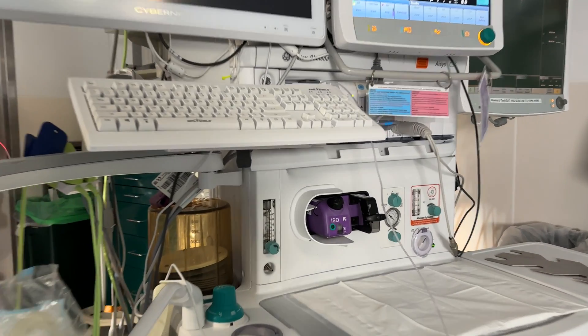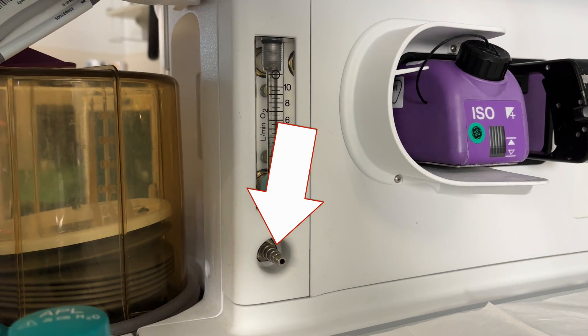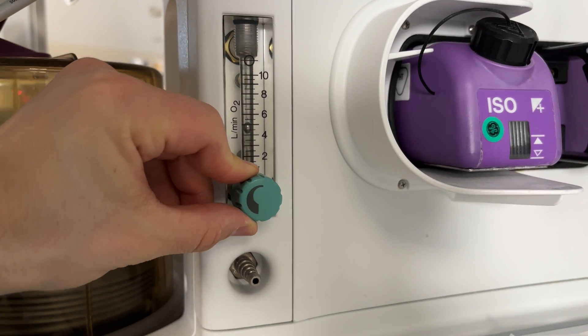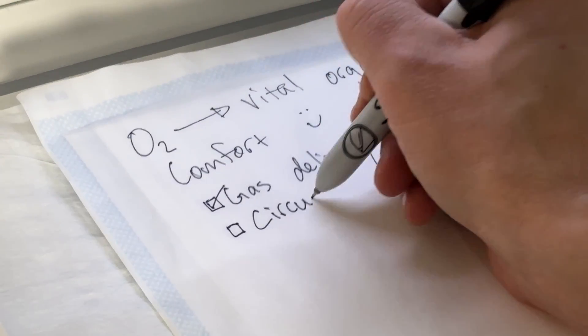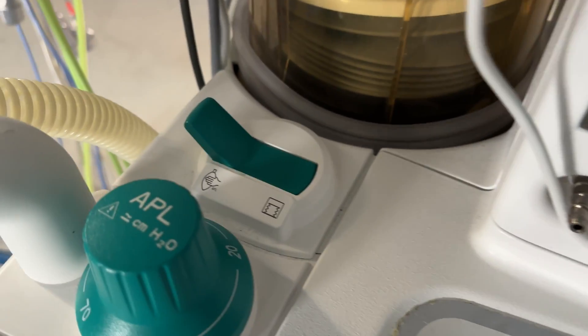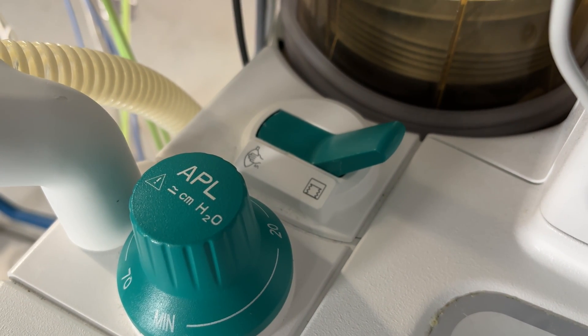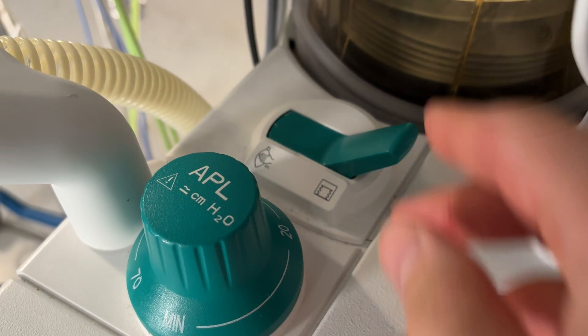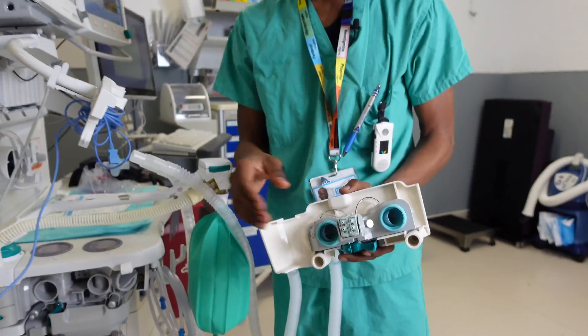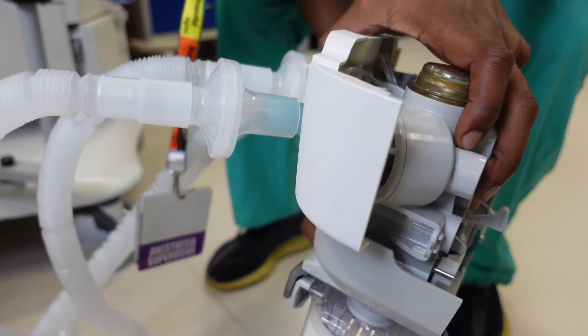In addition to going through the main circuit of the anesthesia machine, oxygen is also piped through this port here, which can be connected to devices like nasal cannulas or face masks, and turned up manually up to 10 or 15 liters per minute depending on the machine. This very official-looking bag-to-vent switch allows the anesthesiologist to toggle between a spontaneous mode, where manual bag ventilation is possible, or ventilator mode, which isolates the bag as well as the APL valve. It's important to be aware of the one-way inspiratory and expiratory valves, which sometimes need to be troubleshot — shout out to the anesthesia techs who help when there's an issue with one of these valves and they need to be replaced on short notice.